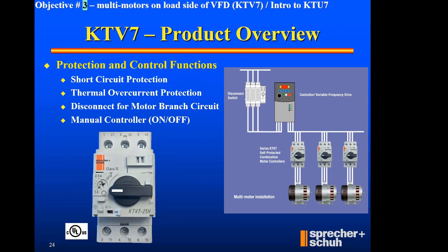I'm moving into objective number 3 to talk about VFD, and we've got this unique controller. If there is a VFD, and the need is for one VFD controlling multiple motors on the load side of that VFD, well, let me introduce you to the KTV as in Victor 7. KTV as in Victor. If we did not have KTV as in Victor, let me see if I can set up the solution 15, 20 years ago. Instead of KTV, the National Electric Code says I need to account for branch circuit protection. I need to account for overload.